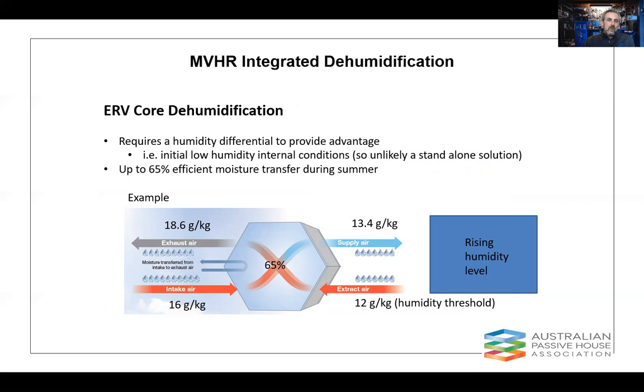So what we've got here is instead of a core that's giving us only sensible or temperature exchange, we do moisture as well. And for good quality cores, we can get up to 65% efficient moisture transfer or recovery. Now, in this example, our intake air, this could be Northern New South Wales at 16 grams per kilogram. Our extract air, which is essentially what's in our building, so bottom right there, is about our passive house humidity threshold, about 12 grams per kilogram.